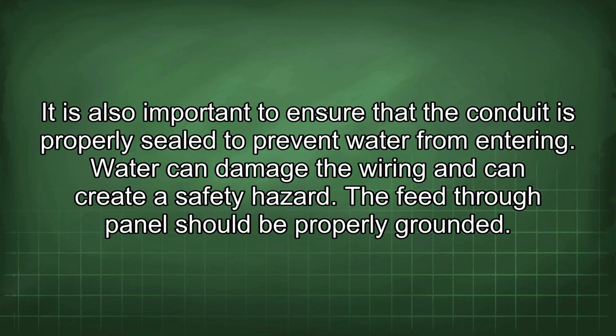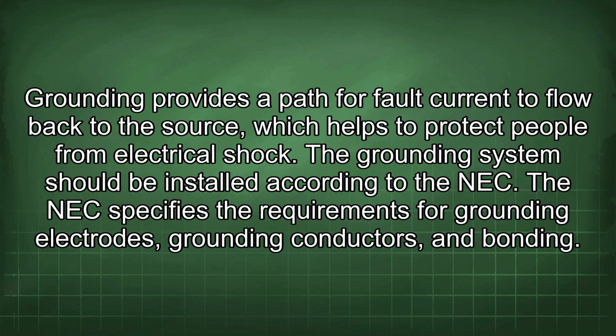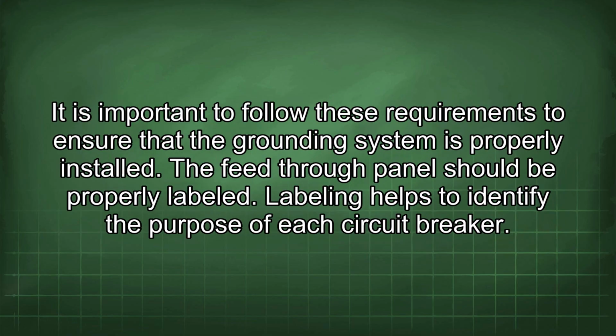The feed-through panel should be properly grounded. Grounding provides a path for fault current to flow back to the source, which helps to protect people from electrical shock. The grounding system should be installed according to the NEC. The NEC specifies the requirements for grounding electrodes, grounding conductors, and bonding. It is important to follow these requirements to ensure that the grounding system is properly installed.